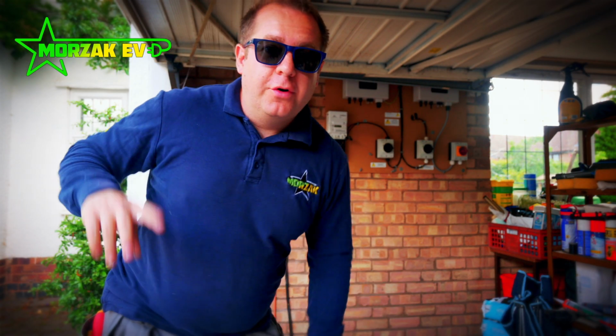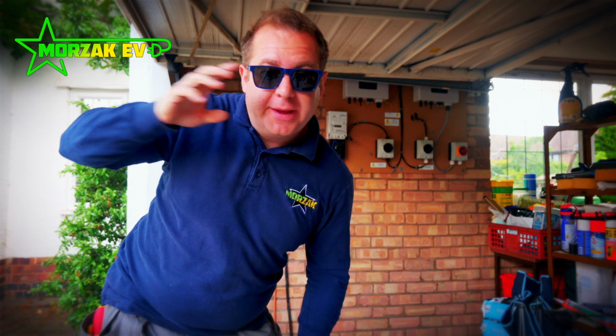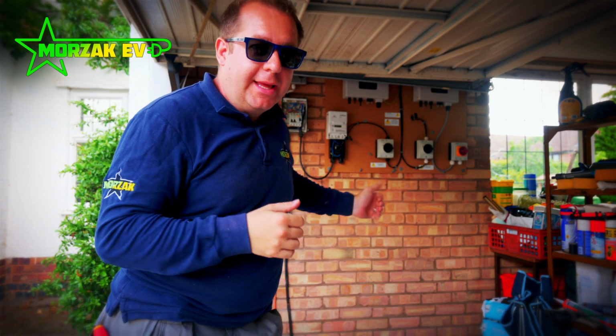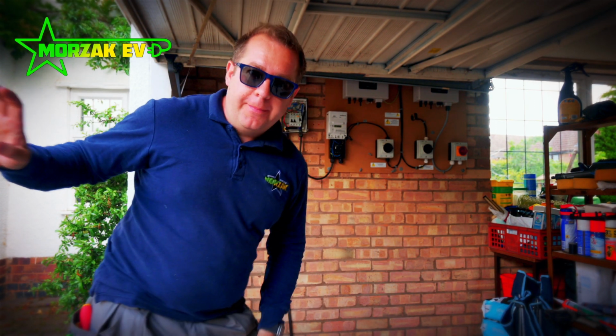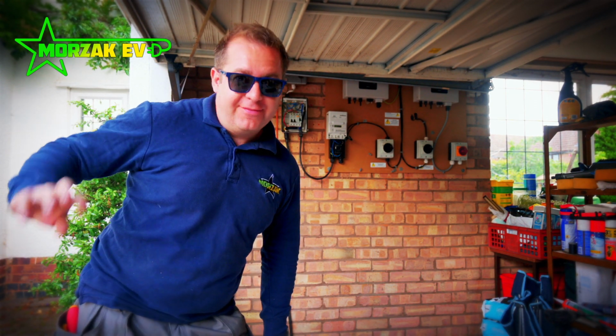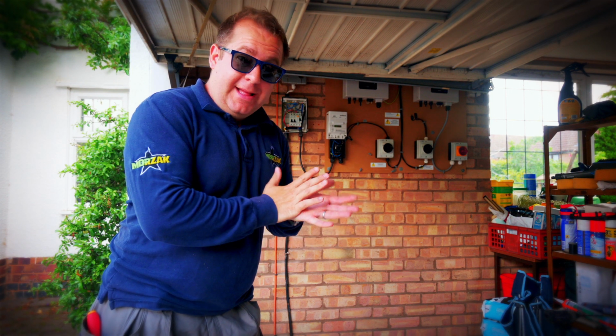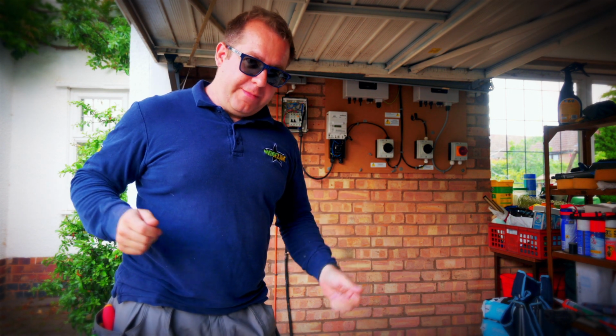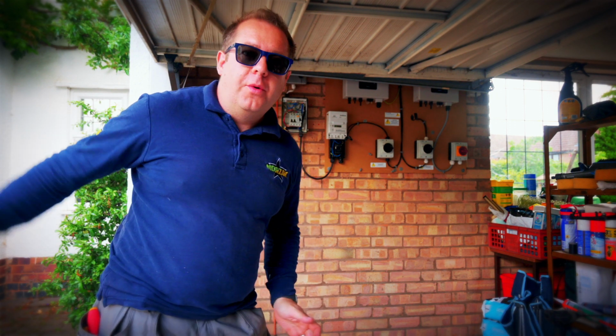Something I forgot to mention on this installation, I've already installed a Zappi on the house, which is picking up the grid supply. That makes installing the Libbi a lot easier, because the Zappi is already measuring the grid, so we can slave the Libbi to the Zappi and it'll pick up on that grid supply. So I haven't got to worry about installing extra CT clamps, a hardwired CT clamp all the way over the other side of the house, or a Harvi, because it's all working off the Zappi's CT clamp sensor.